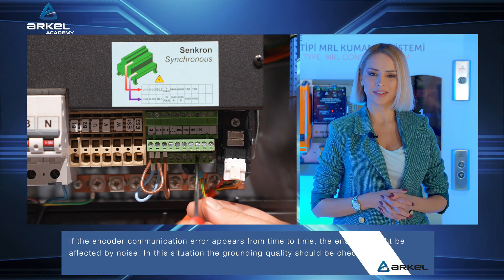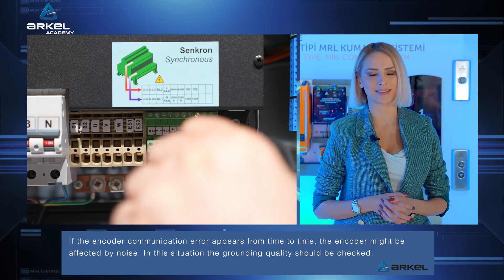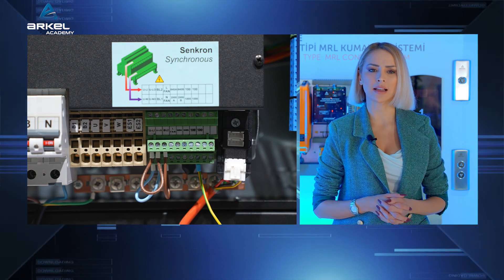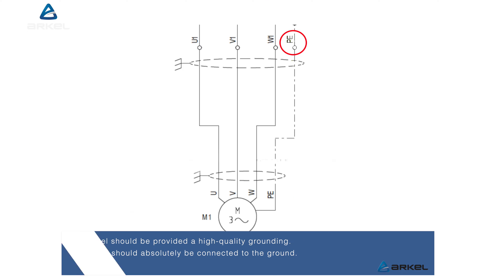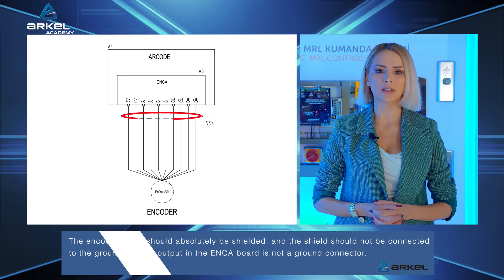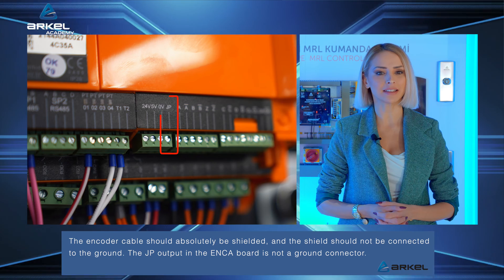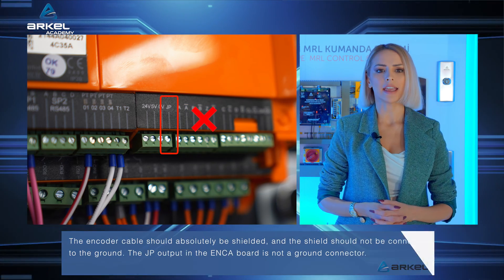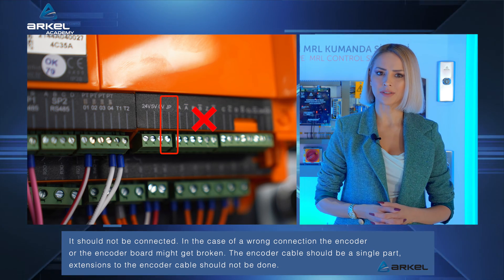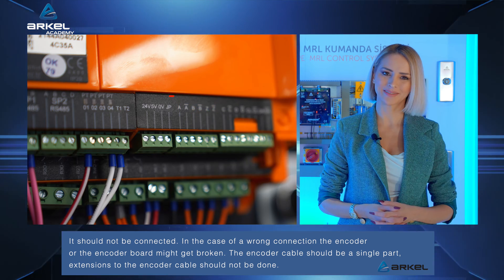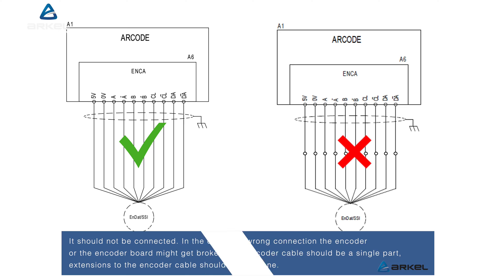If the encoder communication error appears from time to time, the encoder might be affected by noise. In this situation, the grounding quality should be checked. The panel should be provided a high quality grounding. The motor should absolutely be connected to the ground. The encoder cable should absolutely be shielded, and the shield should not be connected to the ground. The JP output on the ENCA board is not a ground connector and should not be connected, as a wrong connection might break the encoder or the encoder board. The encoder cable should be a single part — extensions to the encoder cable should not be done.